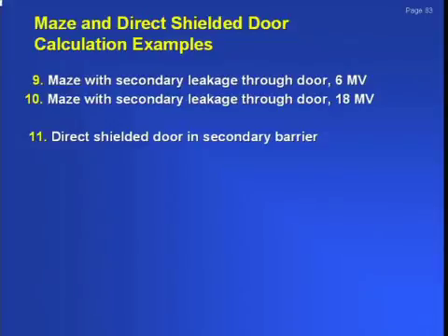If a client says they are going to use an HDR unit in the room as well, do you change your recommendations, or do you add anything to your recommendations if they're going to be using it for HDR? They can do HDR all day in any of my LINAC rooms. Do you put a little room to store the device? Oh yeah, they have to have some way to secure it. But as far as shielding purposes, you are so over shielded in a linear accelerator room for HDR that it's a moot point. But as far as security of that device, that's obviously a different question.